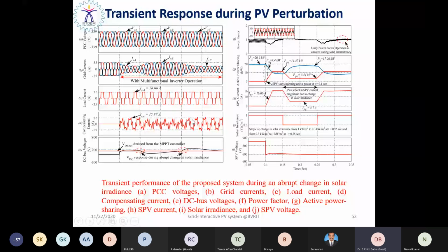And moreover, with the feed forward control loop and the outer voltage control strategy, the DC link voltage always follows the reference trajectory of 690 volts, so the overall dynamic response becomes excellent. This is the grid voltage, and it is in phase with the grid current, so that the power factor of the utility grid becomes unity. And this is the power scenario, the SPV power as well as the grid power. And throughout the case, the DC link voltage is maintained constant. And the DC bus stabilization here is with the help of the feed forward control loop.